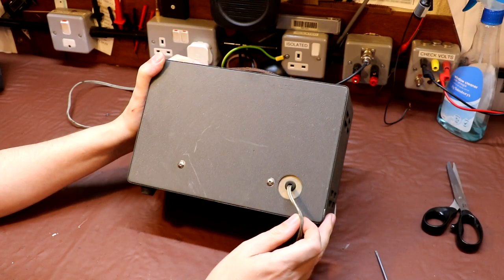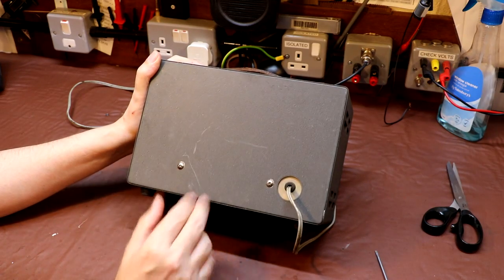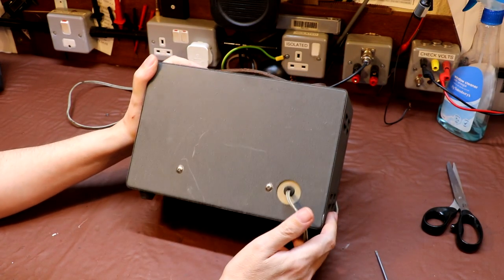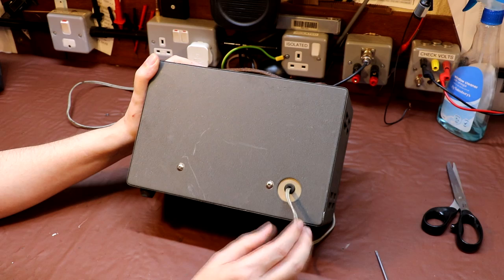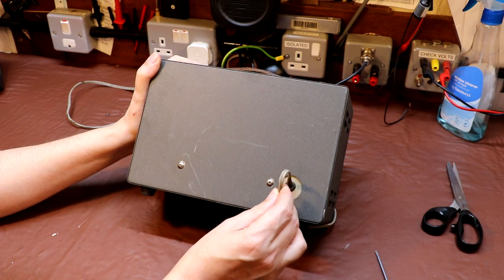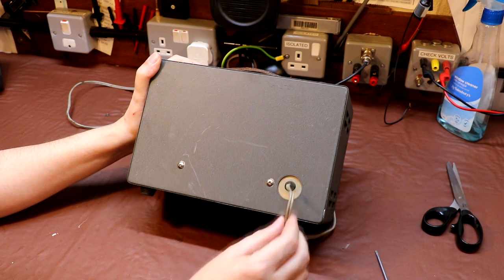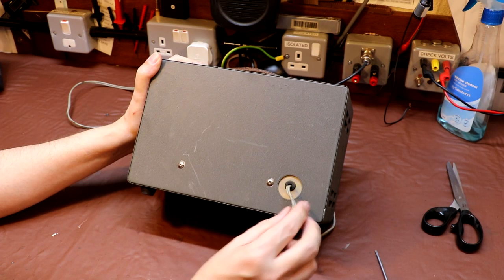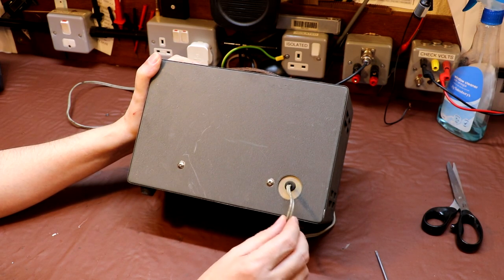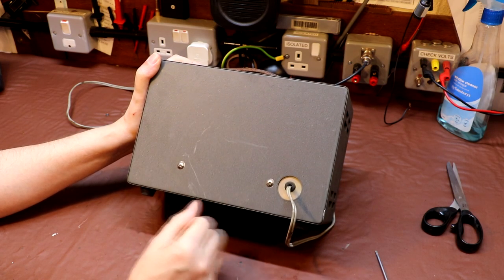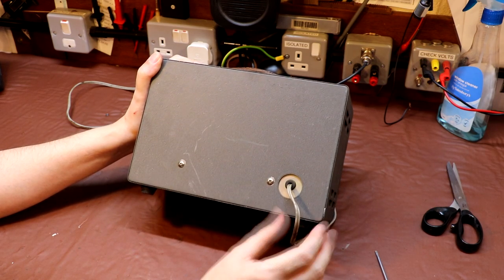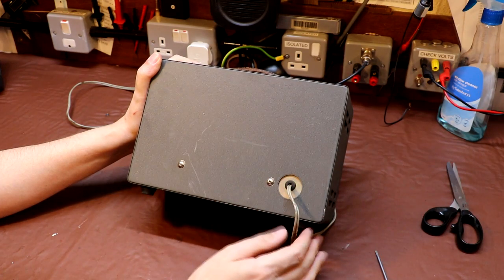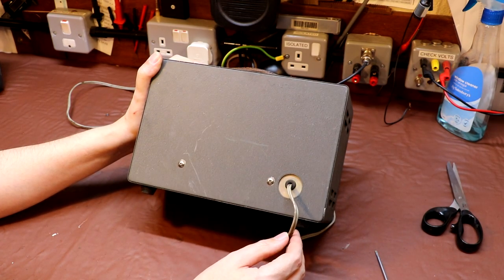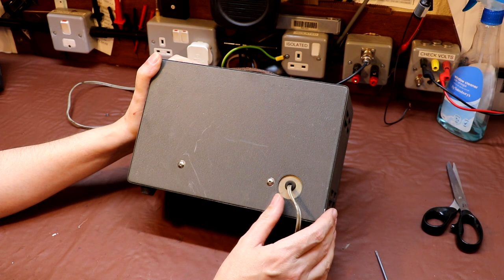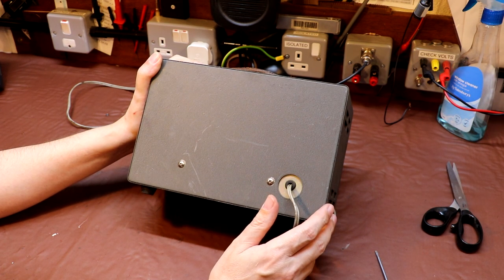So just take a look at the back of the unit, it's really not very interesting. There's no manufacturer's label plates or any of that malarkey. In fact, the only thing we've actually got is the entry here of our 2-core cable. Now generally I will go ahead and replace these 2-core cables on site, and the reason being is because this is a metal instrument, and of course if we get a fault on the transformer, I'm assuming there's a transformer in here, the case could become live and you could receive quite a nasty electric shock.